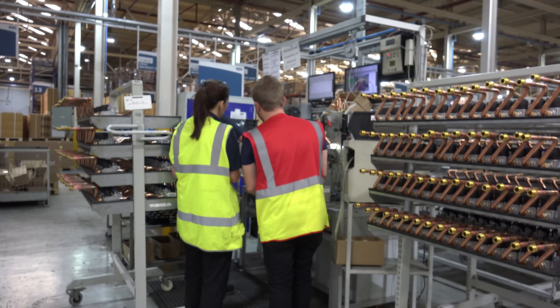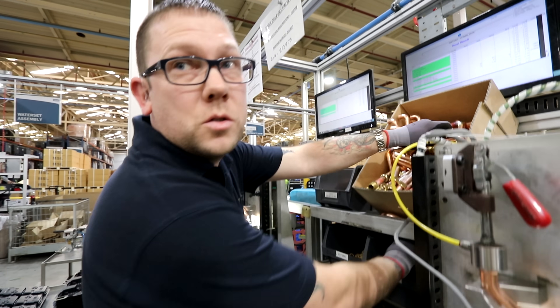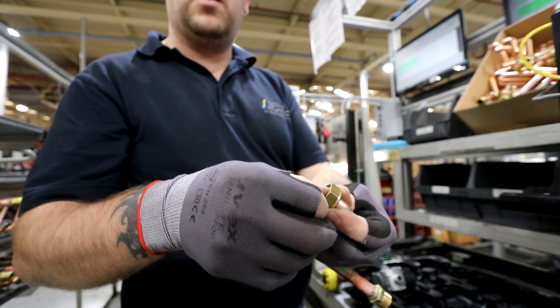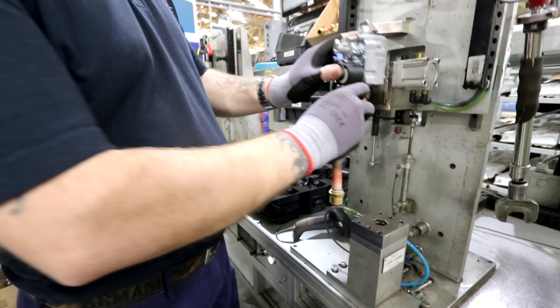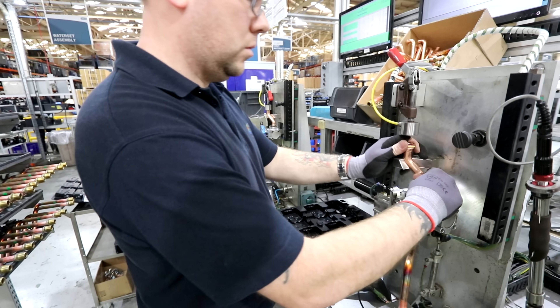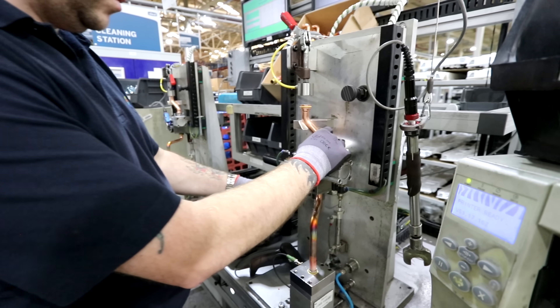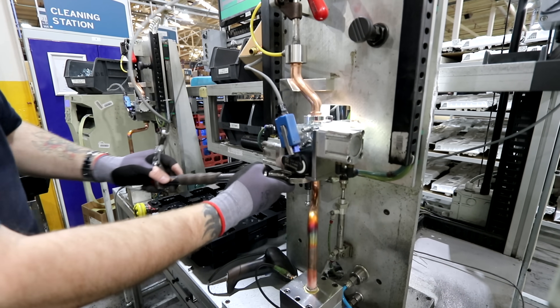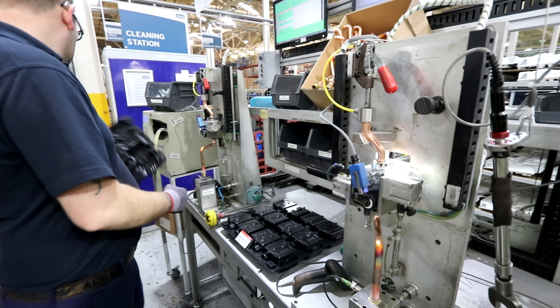I had a quick chat with a lovely old boy called Lee who was building and testing the gas valves. He's building the Logic gas valves — selecting the bottom pipe and nylon washer. First he scans the valve, then scans onto the workstation to confirm he's building the right parts. Lee expertly constructed the gas valve, putting on the O-ring — and there are cameras filming the back of the valve to make sure certain clips are in. Even the torque wrench he's using reads back to a computer to confirm the gas valve has been tightened up properly.